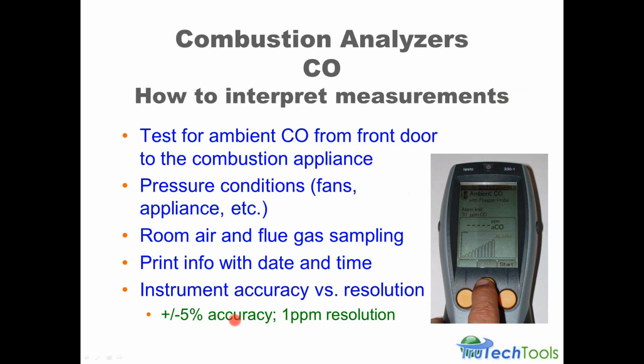Sometimes a question we get is instrument accuracy versus resolution. Resolution is the counts, what can be displayed on the screen, and most of your digital analyzers will be about 1 part per million resolution. However, the accuracy may be about plus or minus 5%. That's usually 5% of reading, which means if you're reading 100 parts per million, it could be plus or minus 5 parts per million. So it could actually be anywhere from 95 to 105 parts per million.